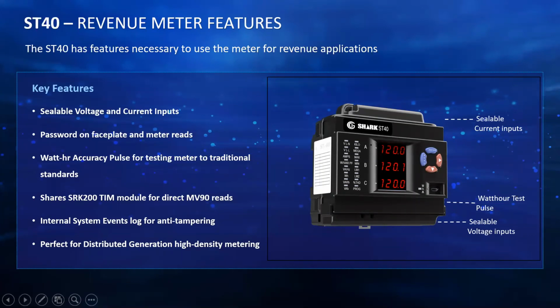Coming to the actual hardware of the meter, it does have sealable voltage and current inputs. It also has a watt-hour accuracy pulse in the front for testing the meter to traditional standards. So, you know, over 2 years, 3 years, 5 years, if you want to make sure that your meter is still accurate, you can use the test pulse to measure the accuracy of the meter, and it will be accurate over long periods of time.